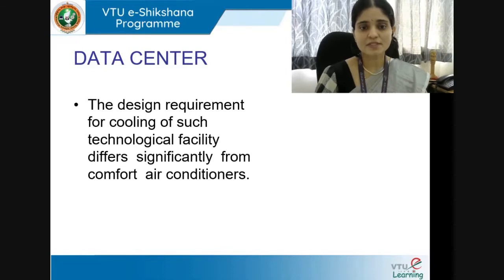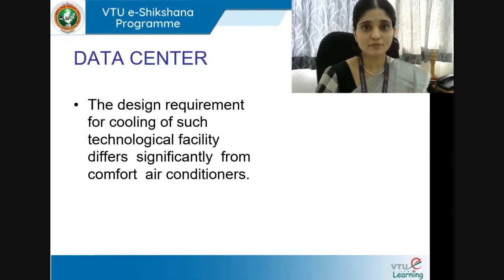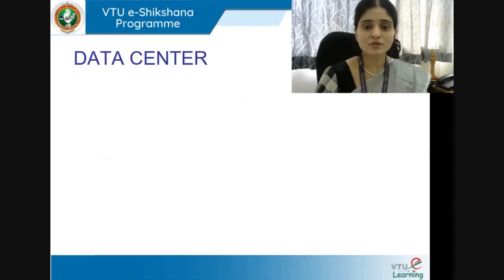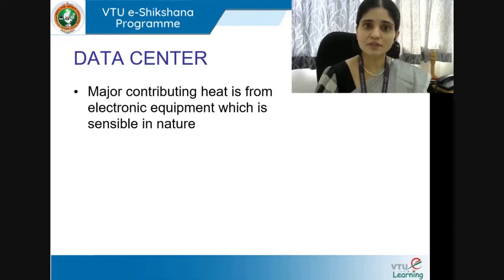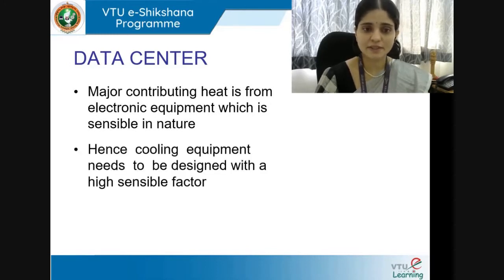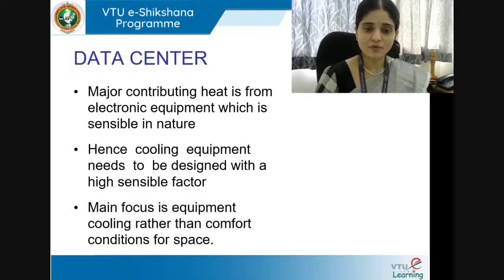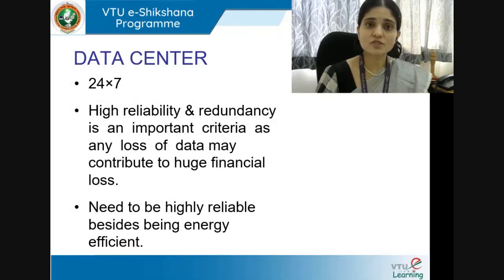Designing for homes, hotels, and theaters differs because comfort AC is the objective there. Here, the major contributing heat is from electronic equipment, which is sensible heat in nature. Hence, cooling equipment needs to be designed with a high sensible heat factor. The main focus is equipment cooling rather than comfort conditions for the space or people, and data centers run 24 by 7 — there is never a stop.